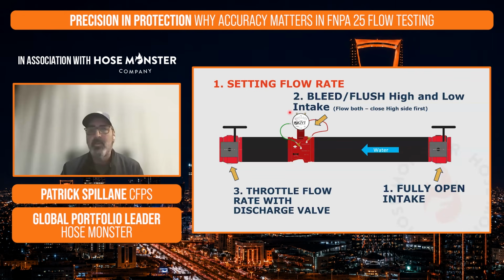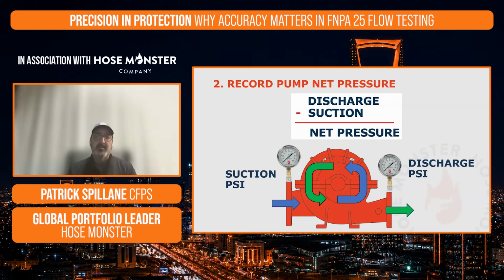going into the meter. And then when we're ready to start flowing, we're now going to use our discharge valve to throttle into our flow rate, right? So we're going to be just slowly cracking that valve open. And as we crack that valve open, we're going to watch that needle slowly move up the dial to get into the exact flow rate that we need to be at. Once we set our flow rate for our test there, so whether we're flowing to 100% of flow or 150% of flow, we want to dial this meter in. Once we have that flow set, that's when we're going to go and start taking our readings.